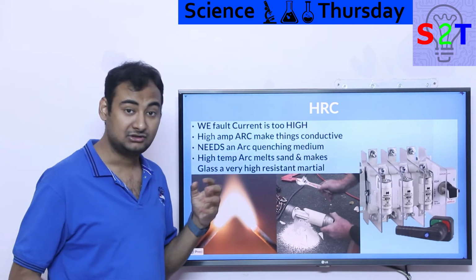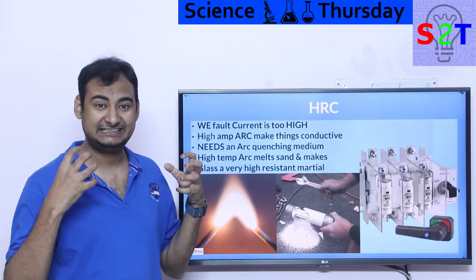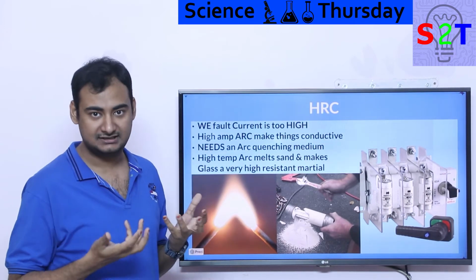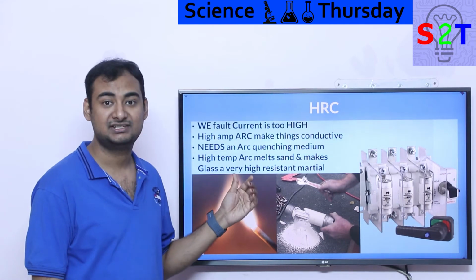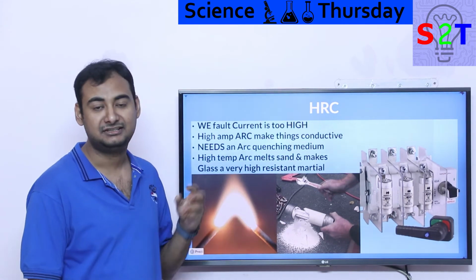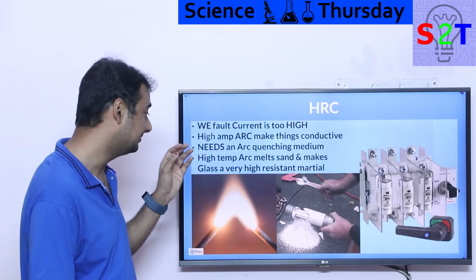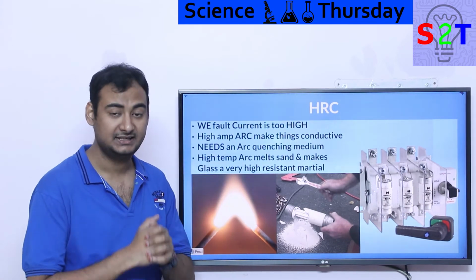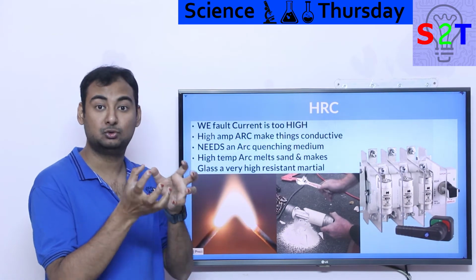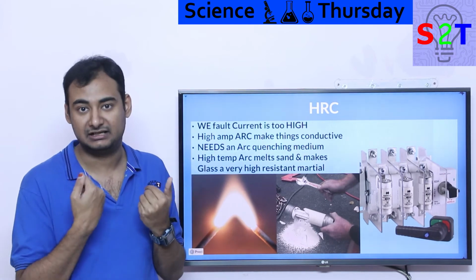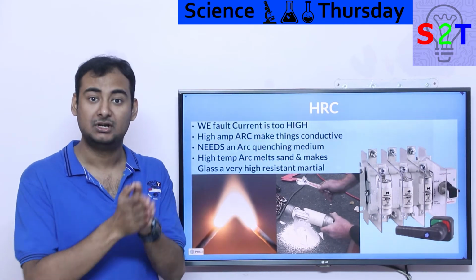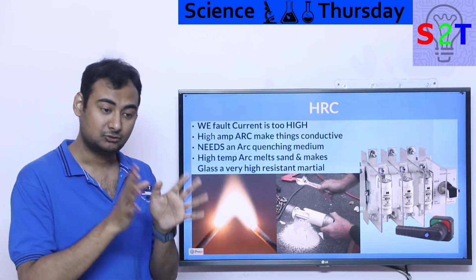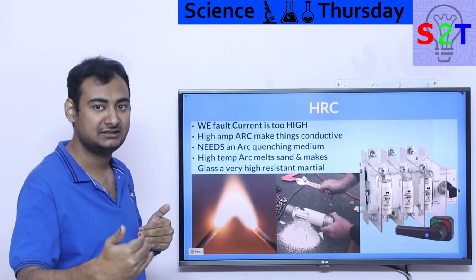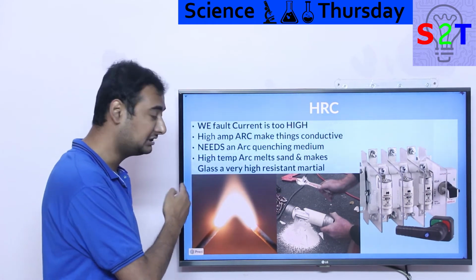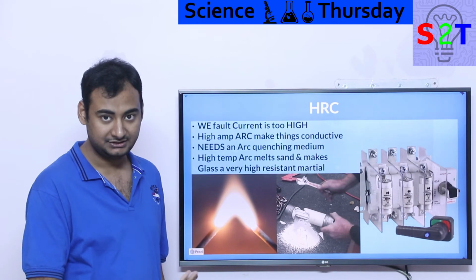So what will happen, because the arc is created, it's so high temperature, it's going to melt the surroundings. The surroundings in this sort of scenario are designed in such a way that they melt and turn into a glass-like substance which will have ludicrously high resistance. Inherently, it's not only cooling the arc simply because it's taking the energy away and phase changing from solid to liquid, it's quenching the system and creating a scenario which is very difficult for an electrical arc to jump across. You have to be very mindful.